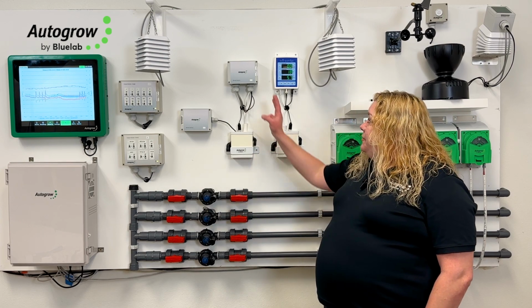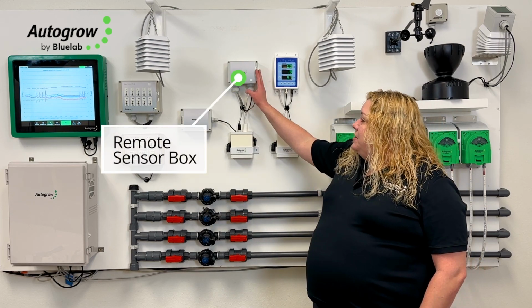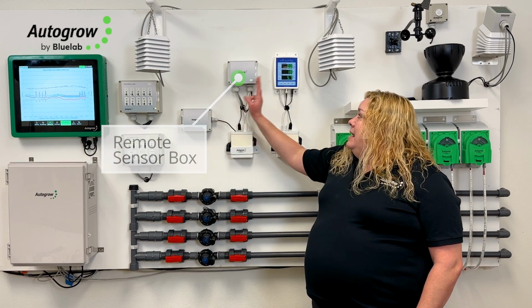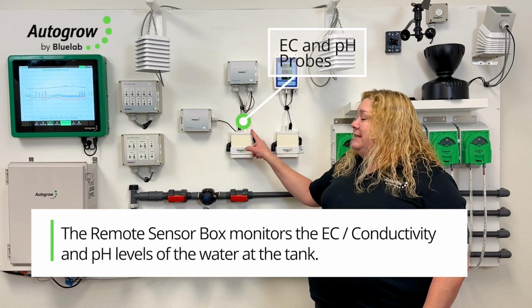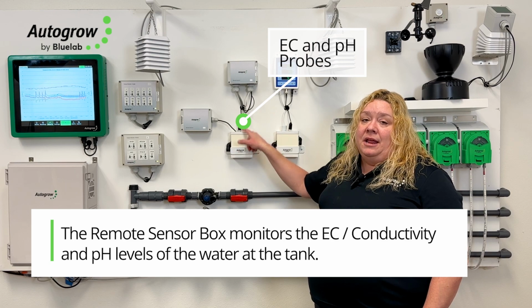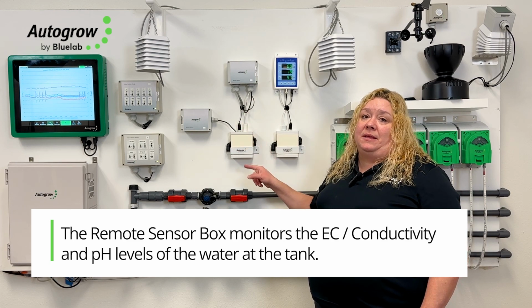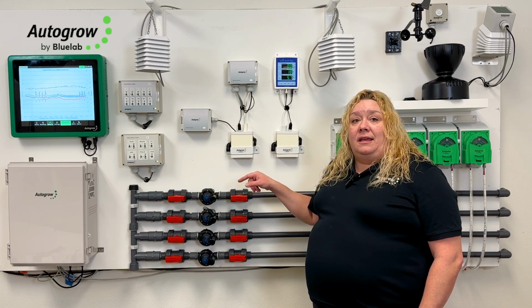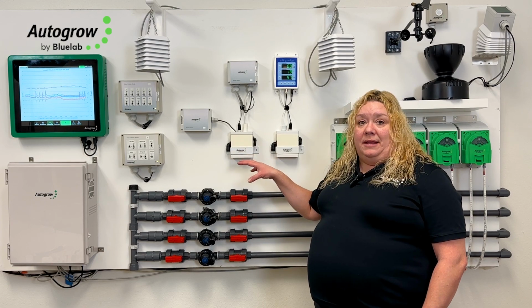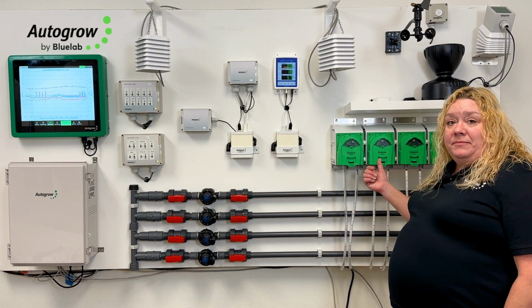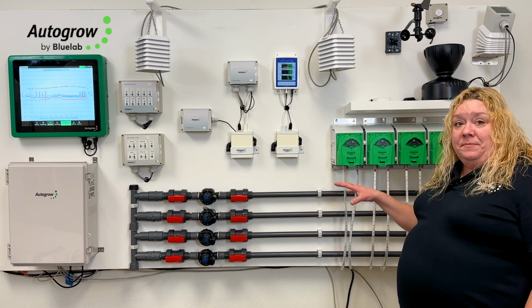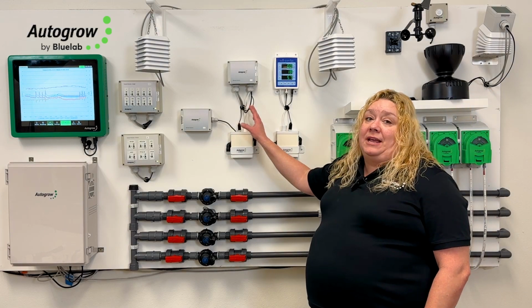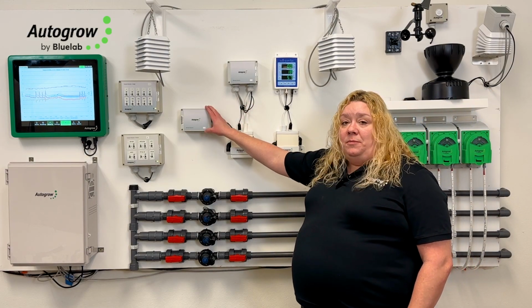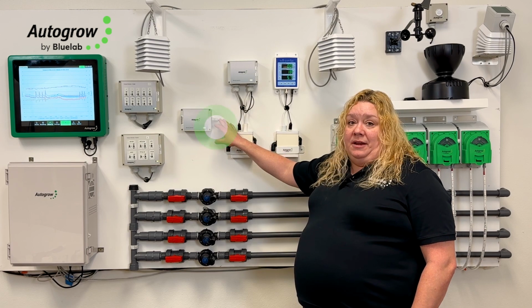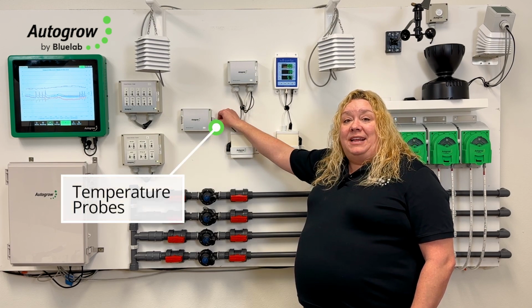So we have a couple different things here that you're looking at. We've got two remote sensor boxes. This remote sensor box has an EC and a pH probe attached to it. So this is monitoring the EC and the pH of the water at the tank, and then we can program it to activate these peristaltic pumps to maintain the EC and the pH in that tank before it goes out to the plants. This remote sensor box has temperature probes on it, and this is for your hydronic heating.